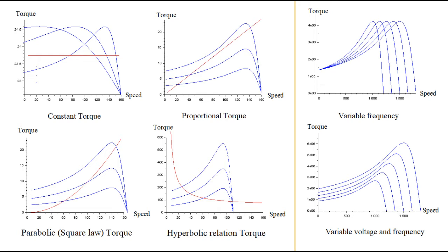The second feature of this mechanical load is that the initial power requirement is low, and as the load catches the speed, at rated speed power is as usual the product of torque and speed. If we look at the first constant characteristics curve, then the value of torque required is 23.8 Newton meters. When the load catches the rated speed of 50 pi or 157 radians per second, then the product of speed and torque is 5 horsepower or 3.74 kilowatts.